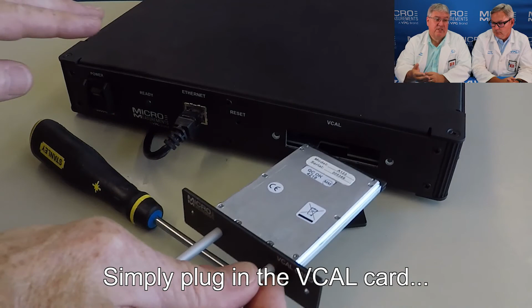I think there's a couple of important things to point out about this VCal card. Number one is that your 8000 scanner can operate without it. You don't have to have it. True. You can scan, record, have all the functionality. You just can't calibrate that scanner. And one of the unique parts about it is that this card will actually inject voltages into the channels. It'll inject these voltages and effectively measure what it sees and compare that to a reference, and then it determines whether or not these channels are within spec.